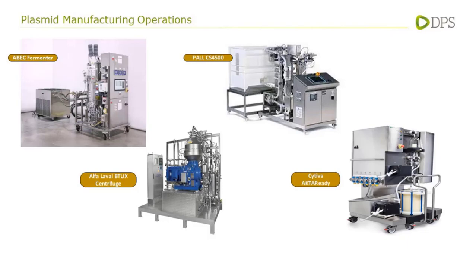Stainless steel equipment obviously requires CIP and SIP, which is not desirable if the intention is to provide a fully single-use facility. One alternative currently being implemented by certain manufacturing companies is the use of a TFF system instead of a centrifuge: the intracellular product is held on the retentate side, and the permeate liquid goes to waste to concentrate the product. This is proving to be an effective alternative to the centrifuge, and by replacing the centrifuge with TFF, it is possible to implement a single-use system to assist with a fully single-use manufacturing train.